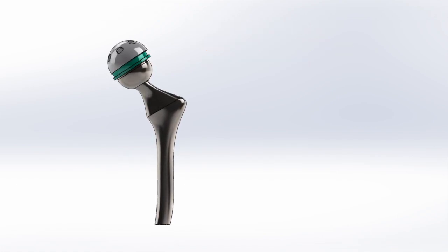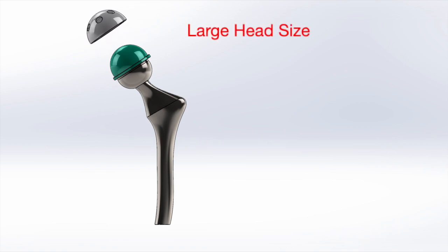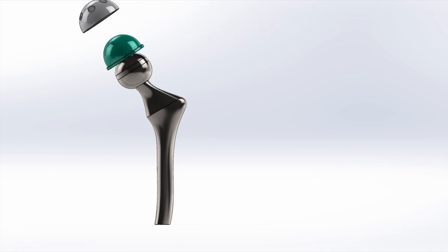Femoral stem design influences how forces are distributed within the bone. Wide, tapered stems distribute stress more evenly, reducing the risk of bone fracture. The head size and bearing surface also play a role. Larger heads translate to greater stability, but because there's more surface, it increases contact stress. Overall, understanding the physics of the hip joint is crucial for designing hip implants that are safe, effective, and long-lasting.